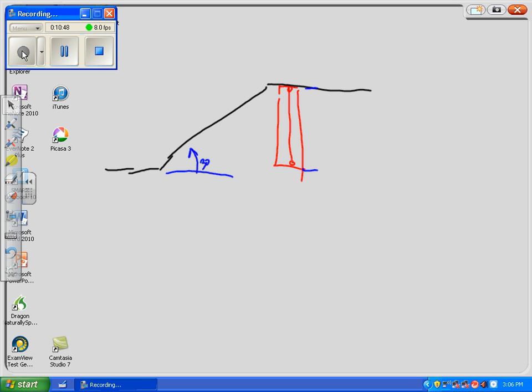There's another one for 45 degrees, but that's so steep that you almost never want to use it. If you put a 45 and a 45 in a conduit, you just put a 90 in the conduit, right? You're only allowed 360 degrees total bend in any conduit run, period. And you never want to have that much bend in a conduit, ever. So those cute little multipliers, they don't work all the time, do they? You still have to get over that object, don't you? What if you want a smaller degree bend or a higher degree bend? Oh my God, we can't do that. Some people can't.